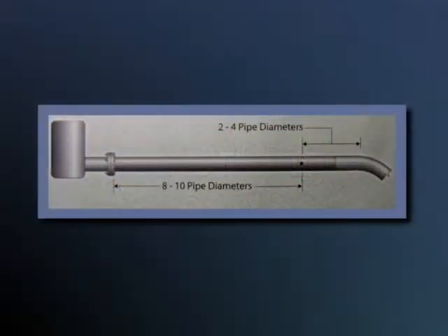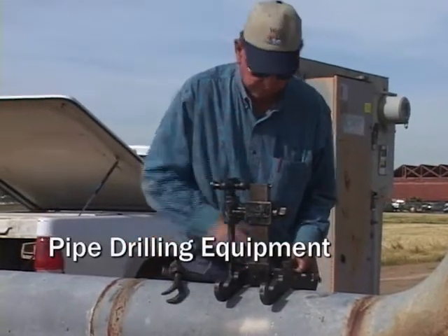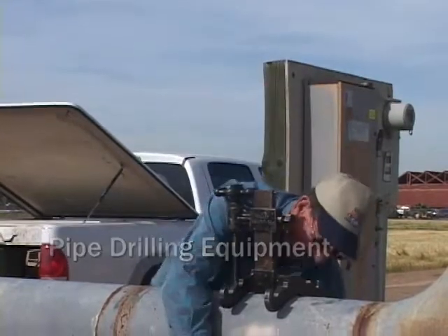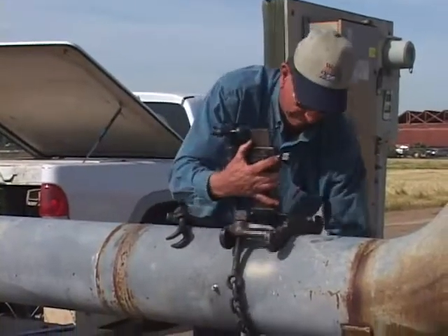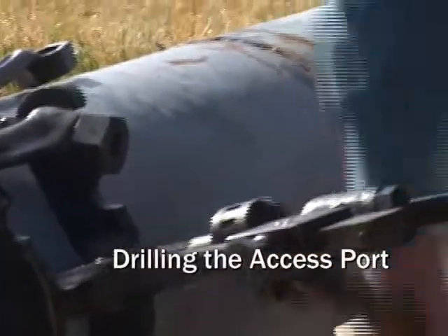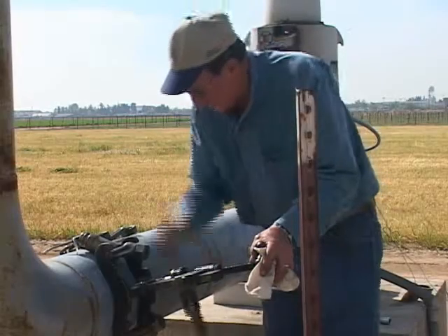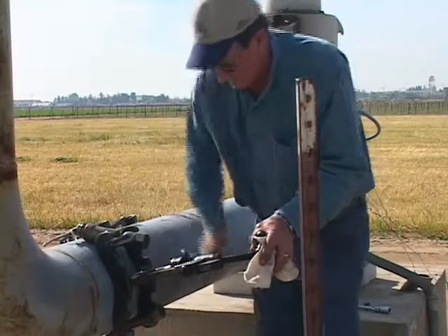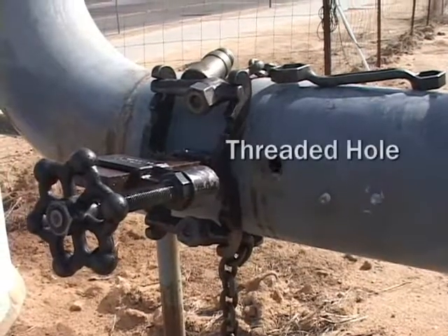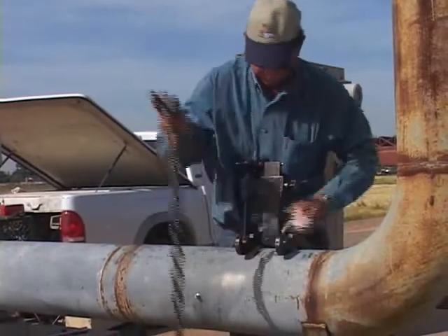The test should be taken 8 to 10 pipe diameters downstream from an obstruction or turn, and 2 to 4 pipe diameters upstream from an obstruction or turn. In this case, Dick must drill an access port to insert the testing equipment. He sets up the drill, carefully lines up where he wants to drill the access, and proceeds. Cutting oil is used to help penetrate the pipe. A threaded hole remains to attach the pitot tube, and a plug is inserted after the test is complete. This same hole may be used for future pump tests. The drill equipment is then removed.